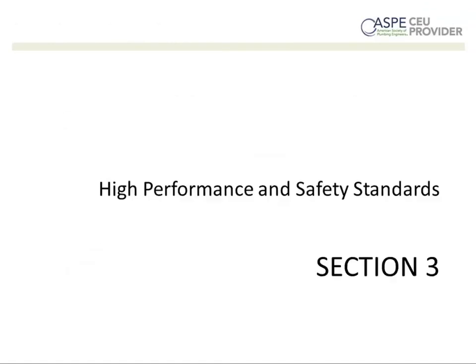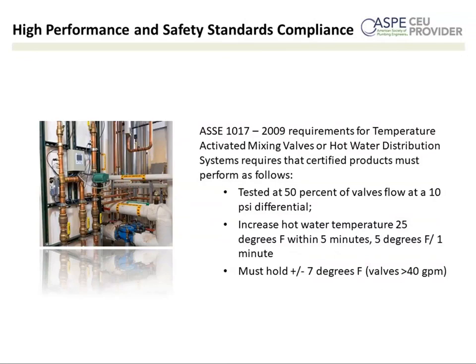Go to the next slide. So we talked about ASSE 1017. I'll just touch on it one more time. This is the ASSE standard that point of source digital mixing valves and distribution mixing valves must comply with or be listed to. And just one thing around minimum flow. All of us manufacturers state minimum flow. To know where a valve is actually tested by ASSE, it's at 50% of the valve's flow at a 10 psi differential. So when you look at a flow chart or a flow graph and see what the flow is at a 10 psi differential, you know that ASSE has tested the valve for control at 50% of that.